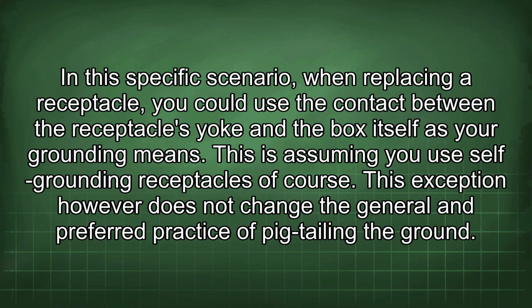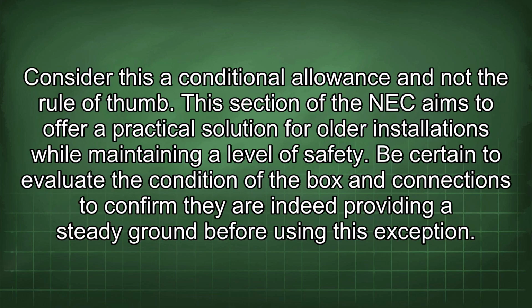In this specific scenario, when replacing a receptacle, you could use the contact between the receptacle's yoke and the box itself as your grounding means. This is assuming you use self-grounding receptacles, of course. This exception, however, does not change the general and preferred practice of pigtailing the ground. Consider this a conditional allowance and not the rule of thumb. This section of the NEC aims to offer a practical solution for older installations while maintaining a level of safety.